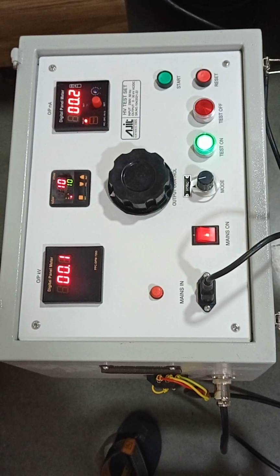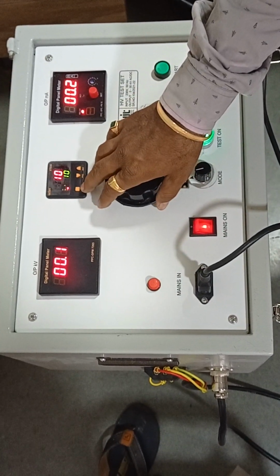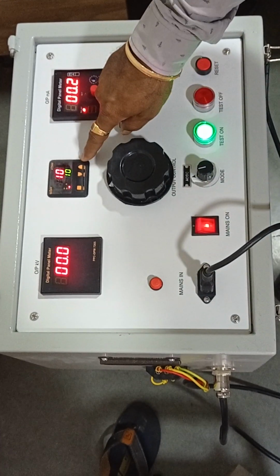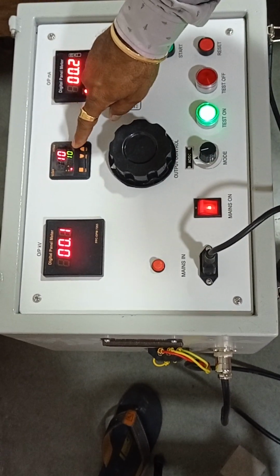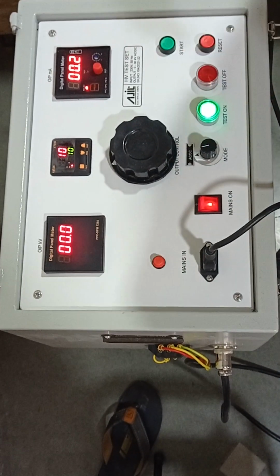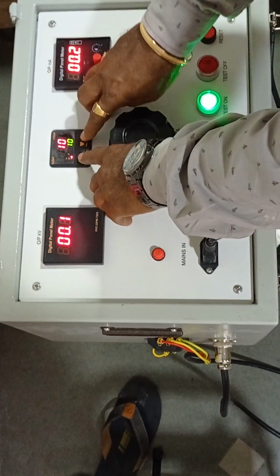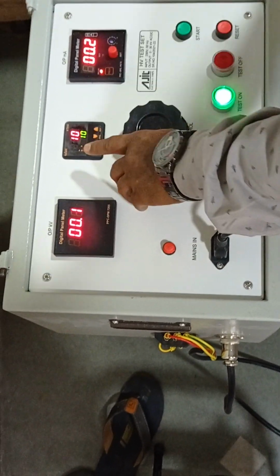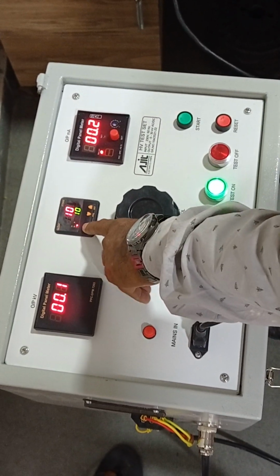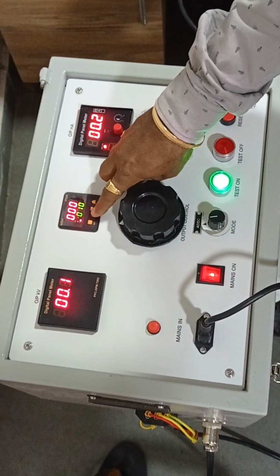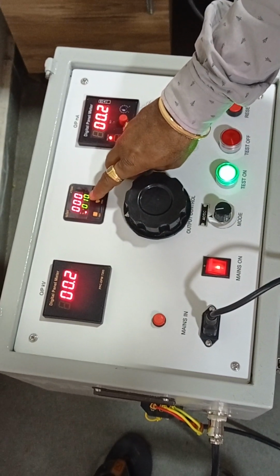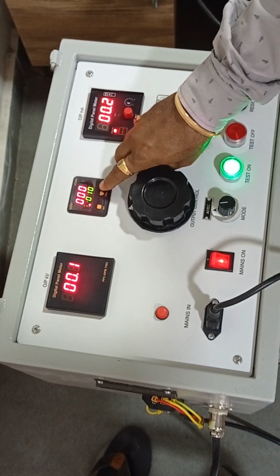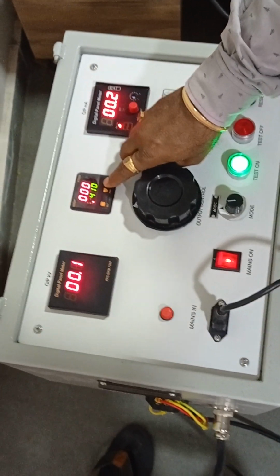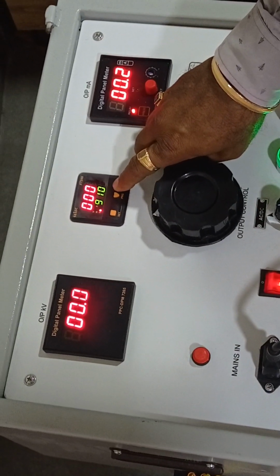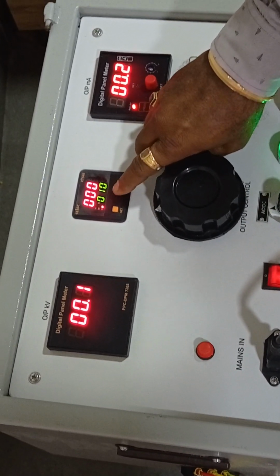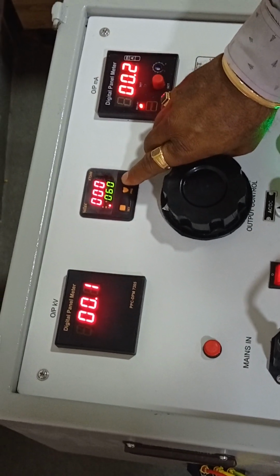Now before I show you the complete thing, understand this timer. This is a timer. One display is for setting and another is for real time measurement or countdown. We can change this value. Press and hold this square button. It will enter into the programming mode. If we want to change this value, we use the up and down keys like this. Hundreds we can change. Again 0. Again press this. Tens, it will be scrolling. We can set it at any value.